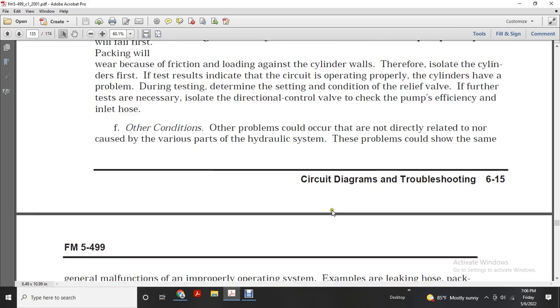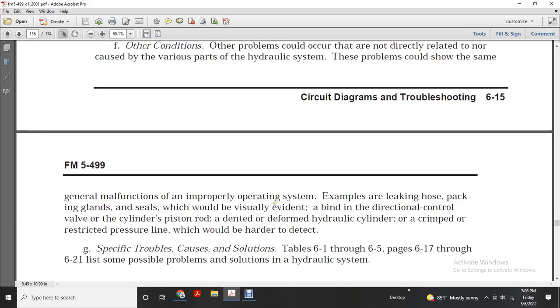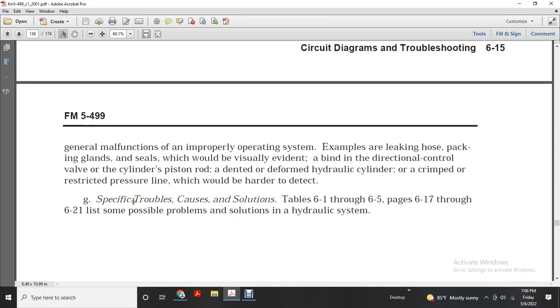The problems could show the same general malfunction as an improperly operating system. For example, a leaky hose or packing gland seals would be visually evident. Binding of the directional control valve, the cylinder piston rod, a deformed hydraulic cylinder, or a crimped or restricted pressure line would be harder to detect. Specific trouble causes and solutions: Tables 6.1 through 6.5, pages 6.17 through 6.21, list possible problems and solutions for hydraulic systems.